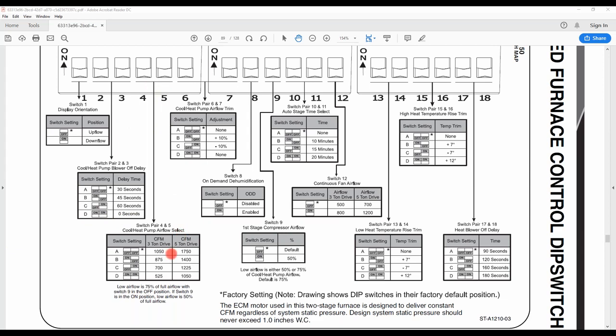Dip switch 4 and 5. Number 4 and 5 are going to be your cool and heat pump airflow selection. So you're going to find here the CFM on a 3-ton drive. The furnaces that are 17 inches wide or 17.5 inches wide will have a 3-ton drive. A 21-inch wide furnace and a 24-inch wide furnace will have a 5-ton drive. So the 40,000, 60,000, and 70,000 BTU furnaces will have a 3-ton drive. The 85, 100, and 115 will all have a 5-ton drive. From the factory, they come set up both in the off position.